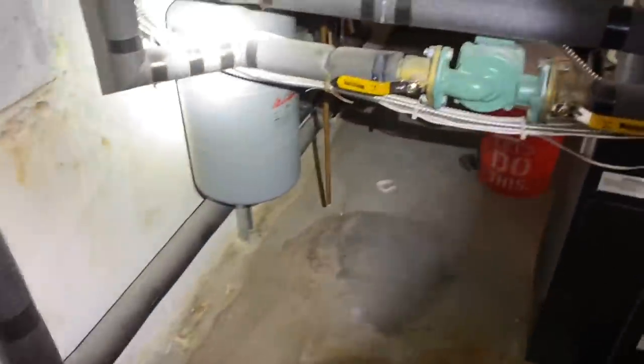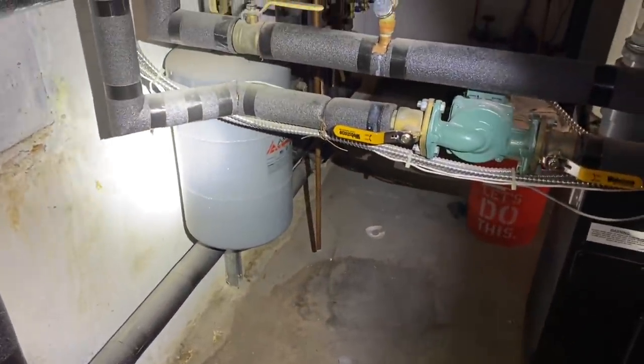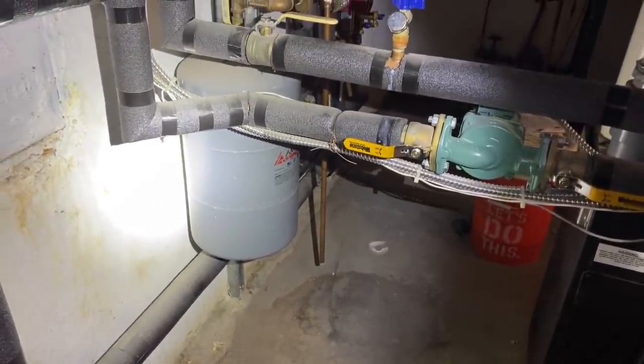The customer mentions the technician who replaced the electric part also noticed a leak on the relief valve, and it's constantly dripping. They probably have a bad expansion tank. The customer says they emptied it yesterday. Mikey asks to see where the expansion tank is, finds it, and says: 'That's your problem - that tank is full.' The customer asks what that means and how to replace it.